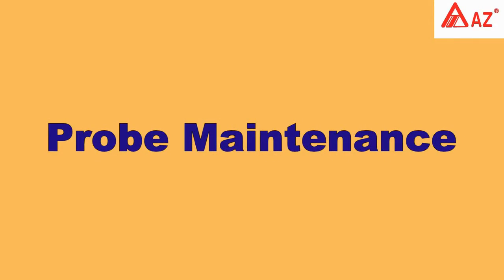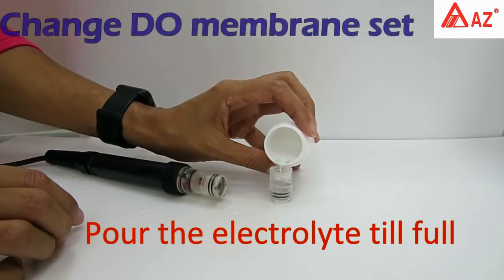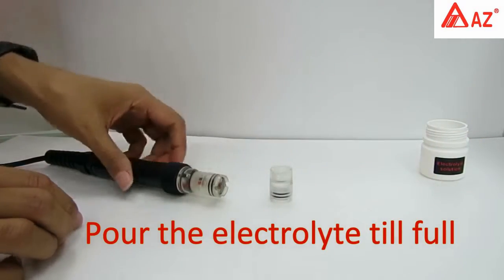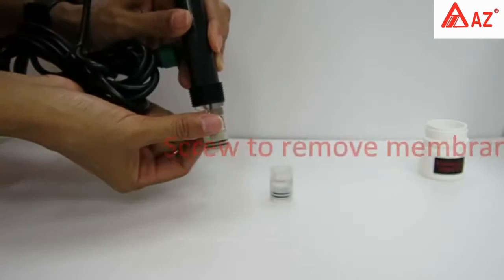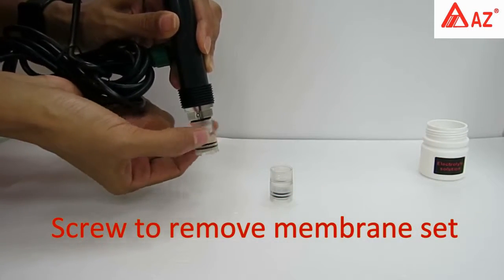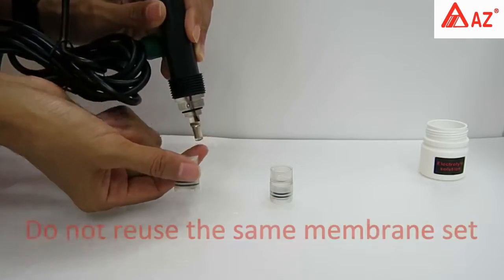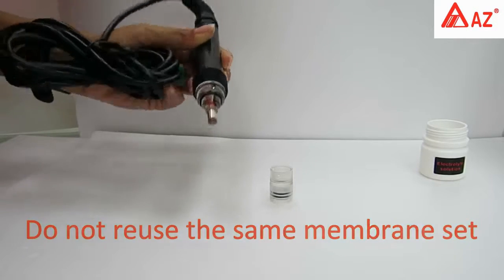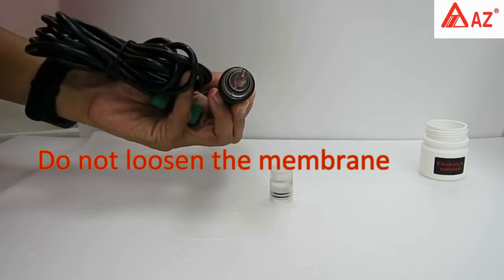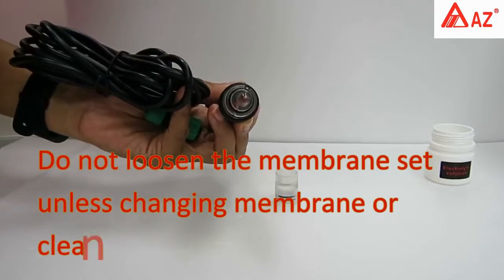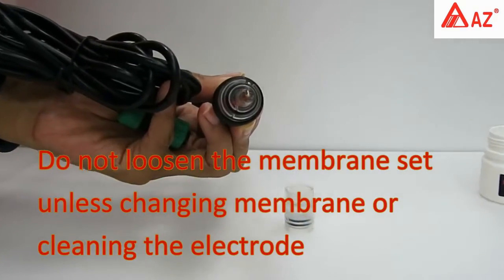Probe maintenance. Pour the electrolyte solution into the new membrane set till full. Remove the membrane set from the probe. Once the membrane set has been removed, do not reuse the same membrane set. Do not loosen the membrane set unless you need to change it or clean the electrode.